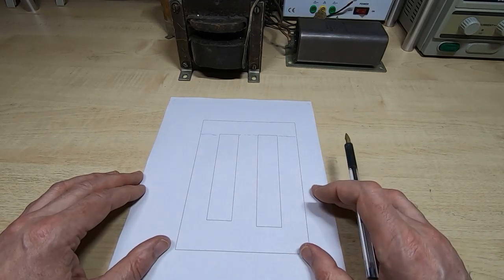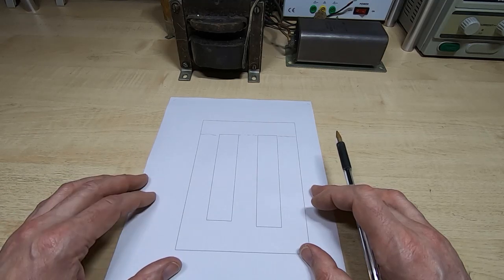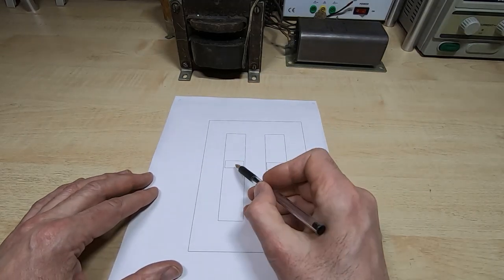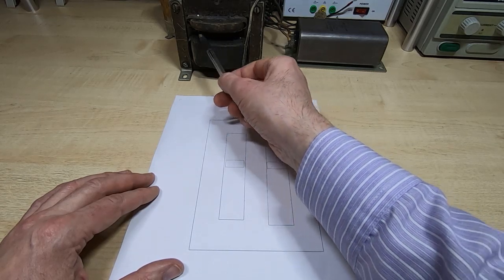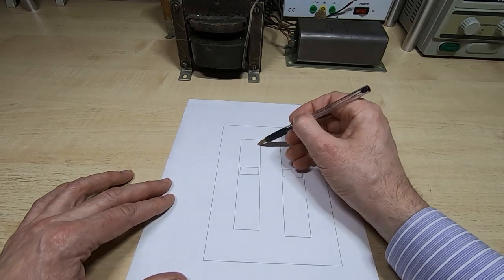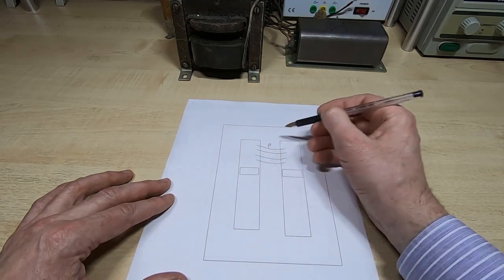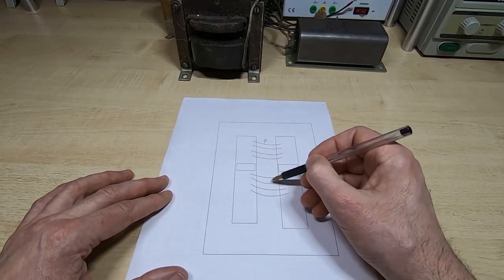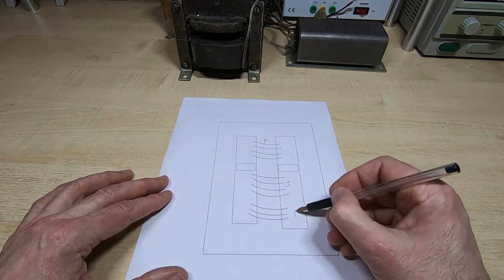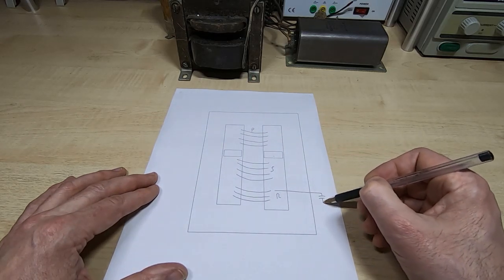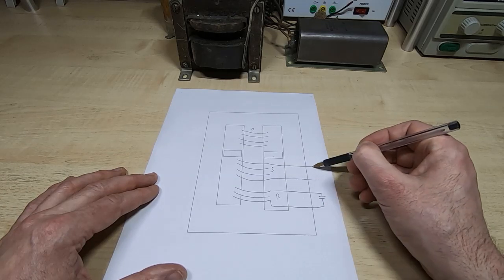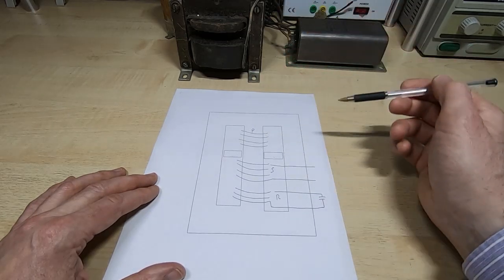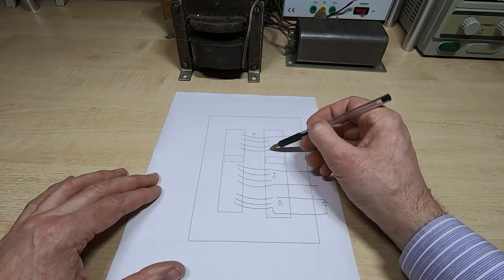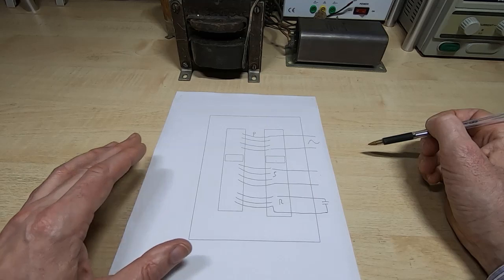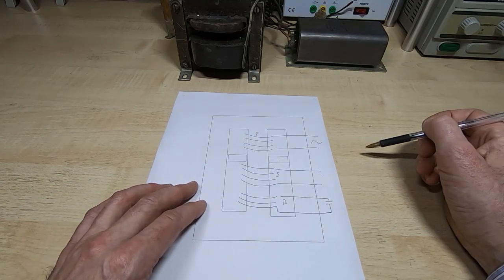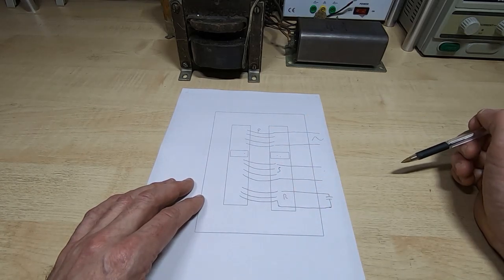Where it varies is there is an addition to ferroresonant transformers that is key to the way they function. They have magnetic shunts, which is what these are, and these are the shunts I showed on the core that sit between the two windings. We have a winding at the top, in this case, and that is the primary. Then we have a winding at the bottom, and that's the secondary. Then there's another winding, and that's our resonant winding. The resonant winding connects to nothing else but the capacitor. The secondary winding is the winding we connect to our load. In the example I showed, it was a rectifier and capacitor. And the primary, of course, is connected to the main supply. That's all a ferroresonant transformer is. The main difference between this and a standard transformer is the inclusion of the magnetic shunts.